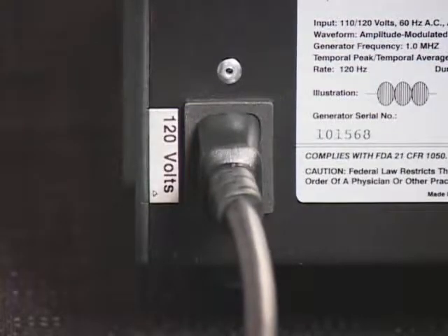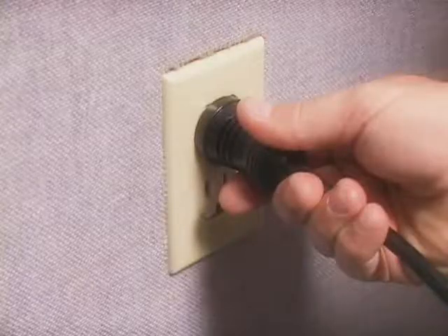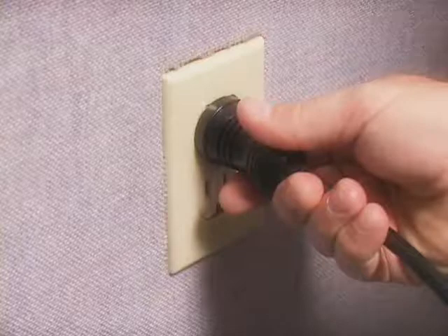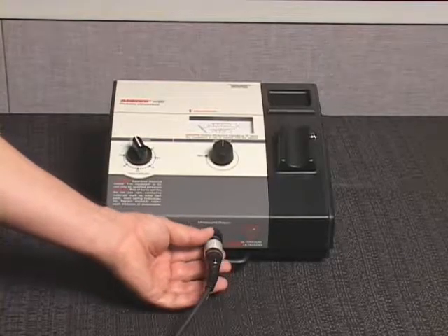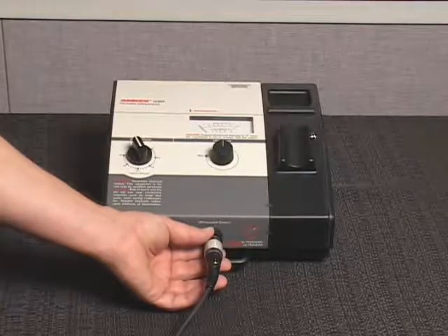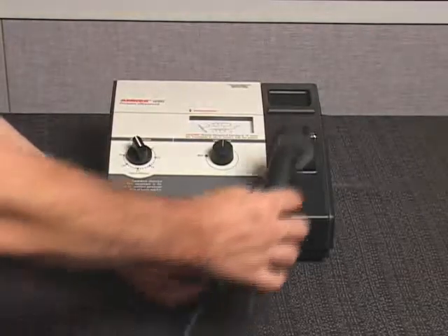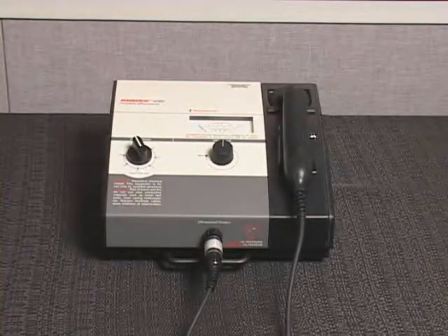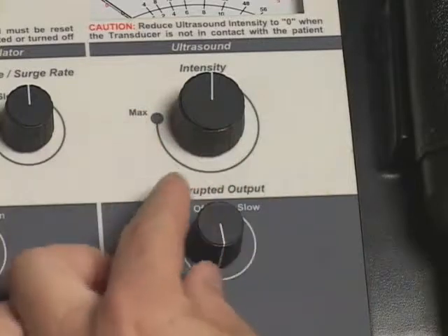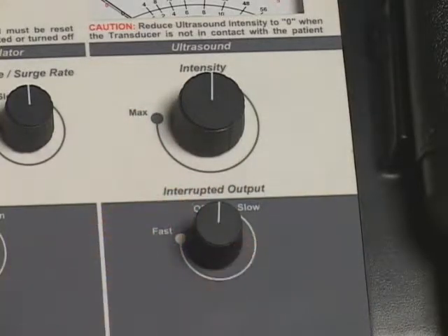to the AC receptacle on the back of the unit and insert the power cord plug into a properly grounded AC receptacle. Connect the assigned ultrasound transducer to the generator's ultrasound output transducer connector and place the handle in the transducer cradle. Reduce the ultrasound intensity control to 0 and set the ultrasound interrupted output control to the off position, enabling the audible click.